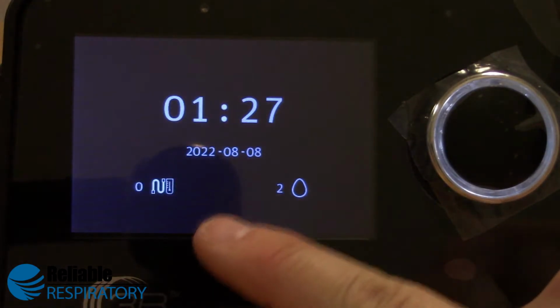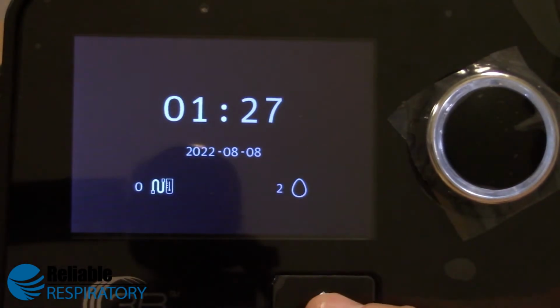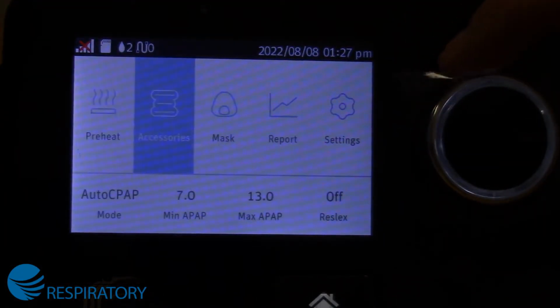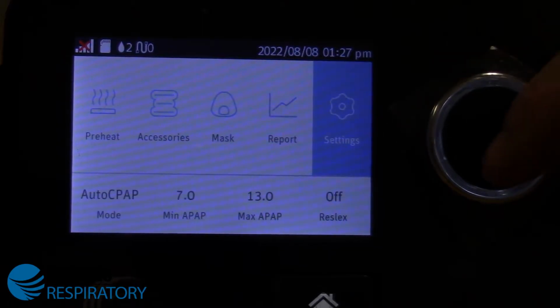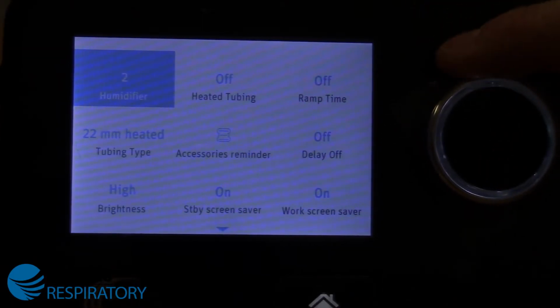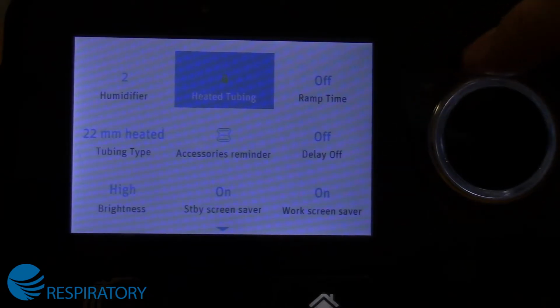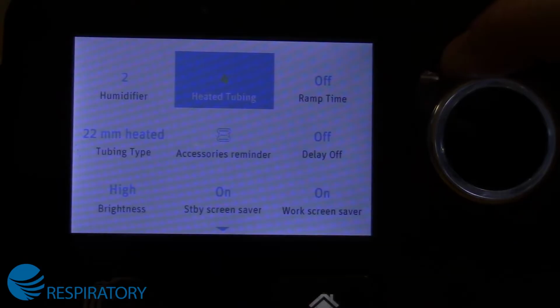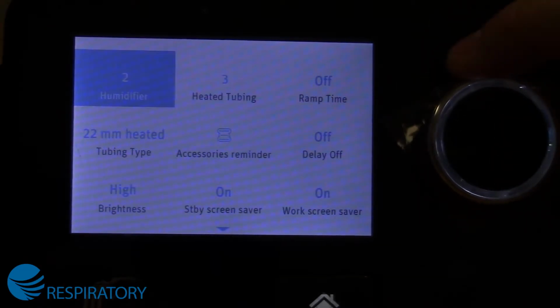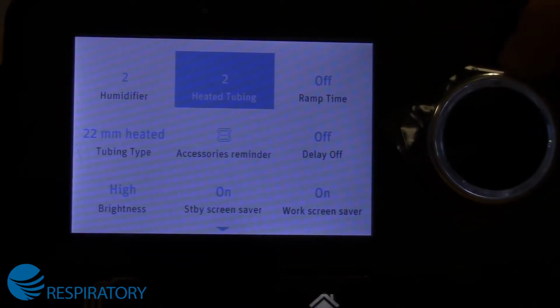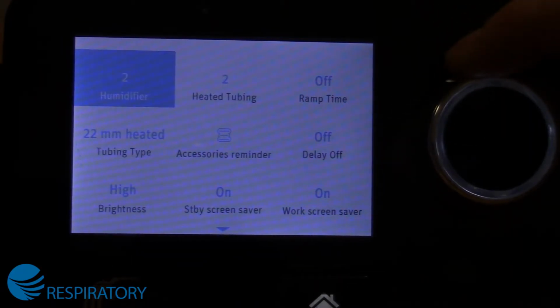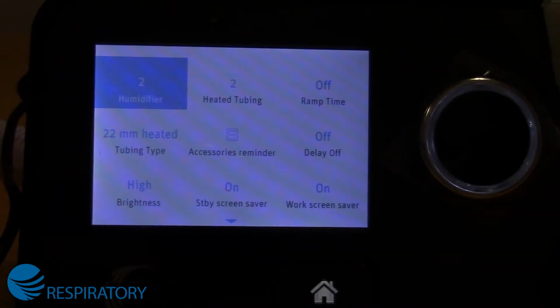To adjust your heated tube and your heated humidifier options, hit the home screen, toggle the dial until you get to settings, click in. Now both your humidifier and your heated tubing settings are from off to as high as 5, so basically 1 to 5 on both. For a start point, we recommend starting both the heater and the heated tubing at a setting of 2 and adjust accordingly. The humidifier setting, just like the heated tubing, goes from 0 to 5. 5 being the hottest and most humid setting, and off being basically no heat whatsoever. This is a personal preference setting.